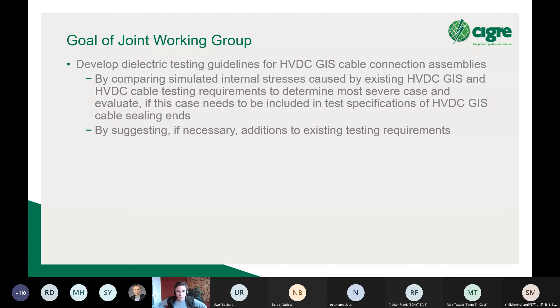Well, the general approach that we have is to model the GIS cable connection assemblies and then simulate the stresses from the cable test requirements and the GIS test requirements in a specific test object arrangement. Then use predefined criteria to compare these different stress profiles and use that to formulate a recommendation. The idea is to do this for the designs for cable connection assemblies from different manufacturers. Different manufacturers are taking part, fortunately, in our working group. And then also do this for the different types of tests, so qualification tests, manufacturing tests, and commissioning tests.